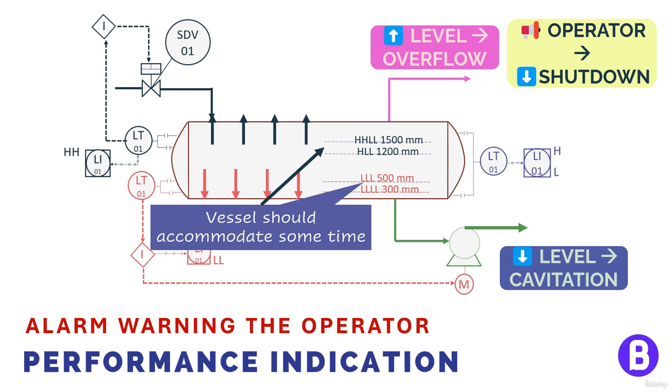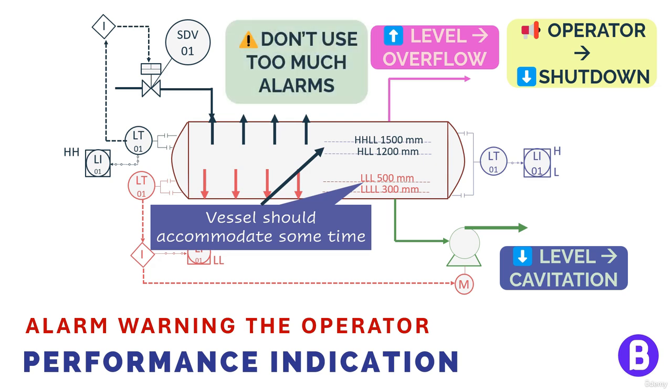Alarms are also used in pressure and temperature or in flow measurements. It's of course better not to add alarms on all instruments, as this may cause a disturbance to the operator. Too many alarms may lead the operator to neglect lots of alarms. This is highly important to consider because neglecting some alarms which are critical may cause operational issues. That's why it's better to add the alarms that are necessary and critical. Otherwise, we won't need to add these alarms as this may cause disturbance.